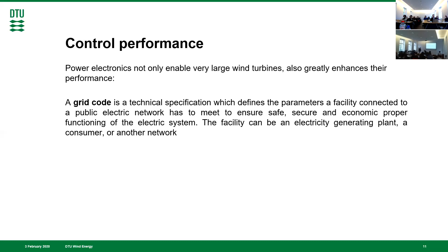It started with what we call grid following. By grid following, it means there's already a grid created—somebody is generating the frequency and voltage of the grid, and the generator in the wind turbine has to connect and inject current with the same angle. I saw there's a grid forming session tomorrow, so I won't go too deep into that. The first wind turbines connected to the grid had, to some extent, P and Q control—some even earlier than that didn't have those requirements at all.